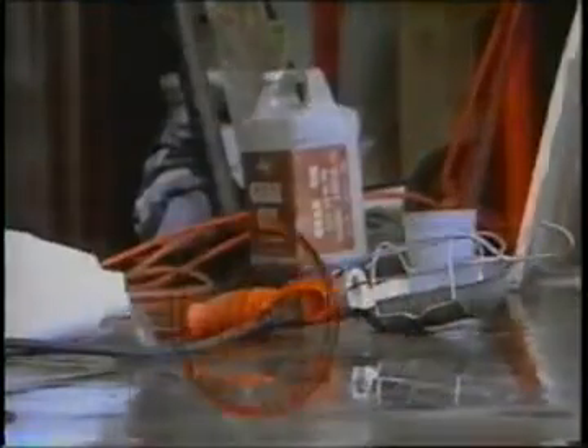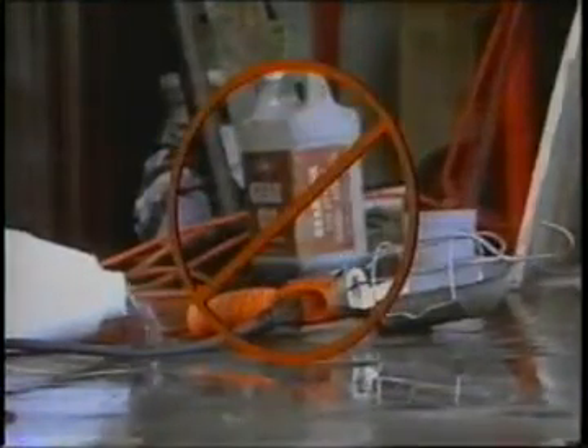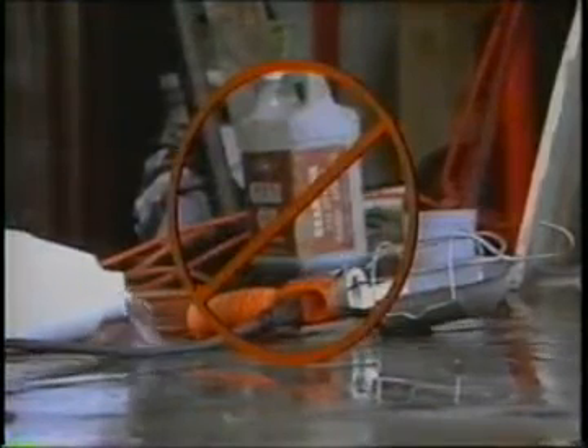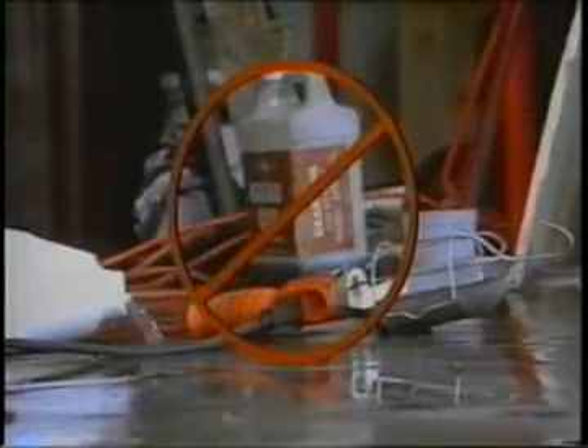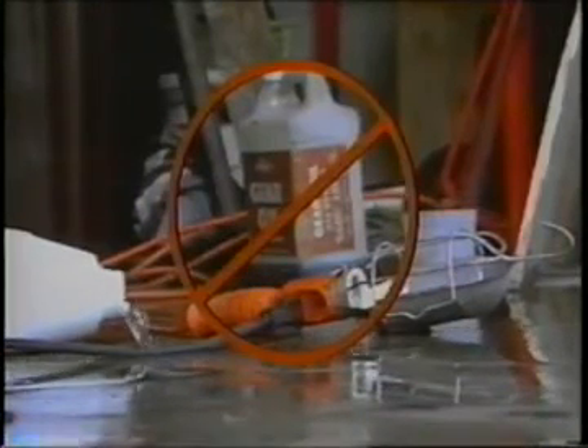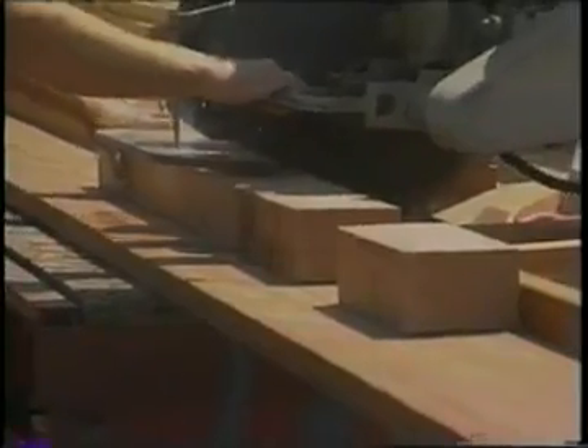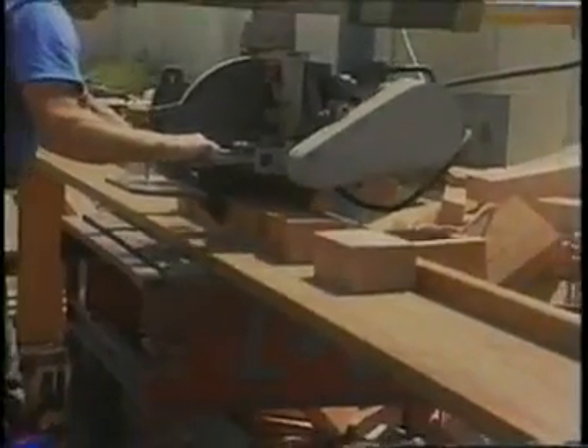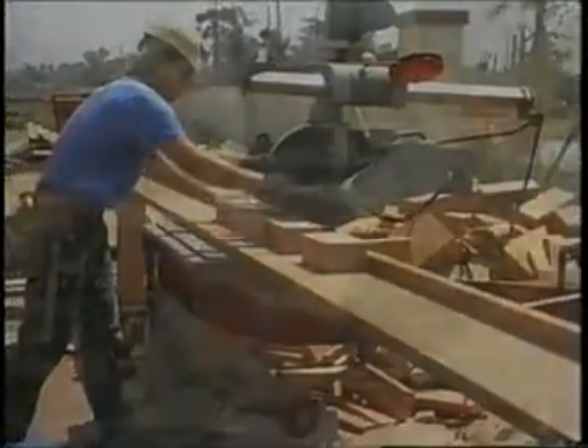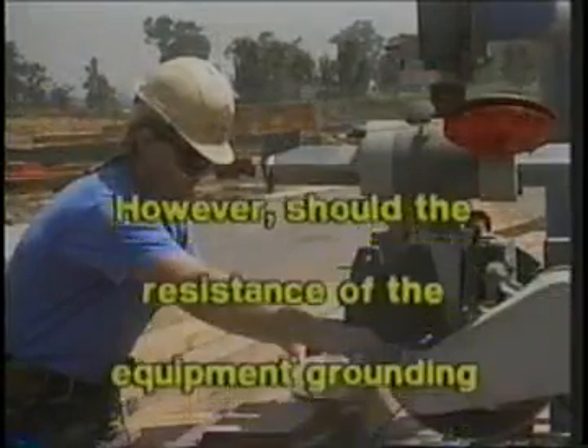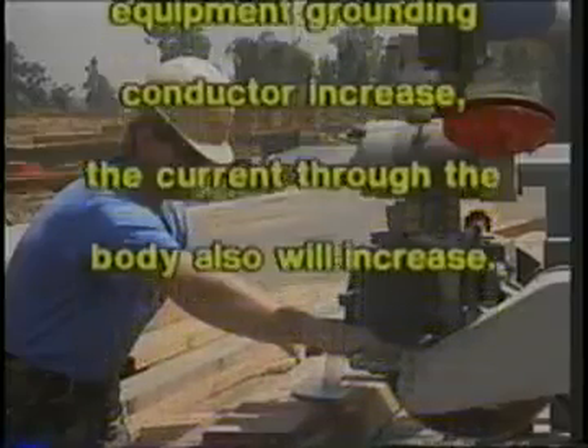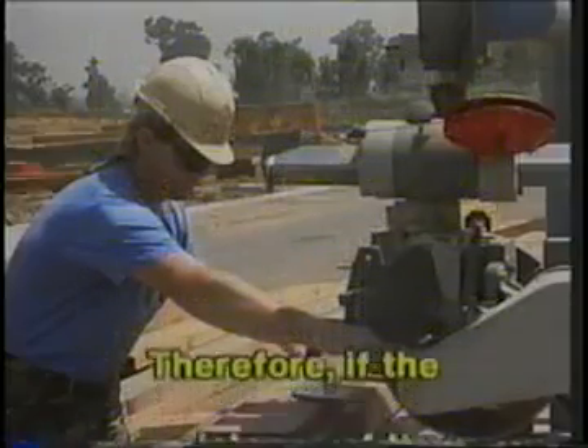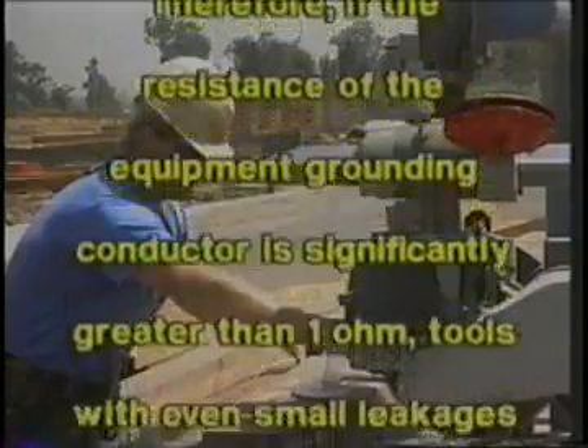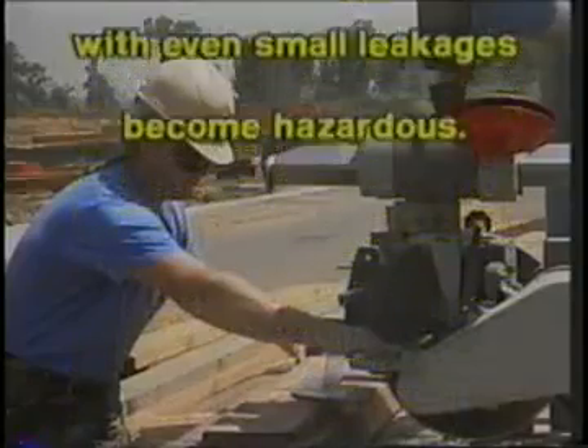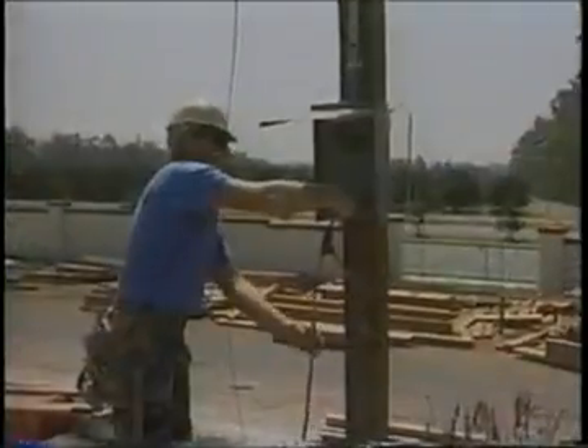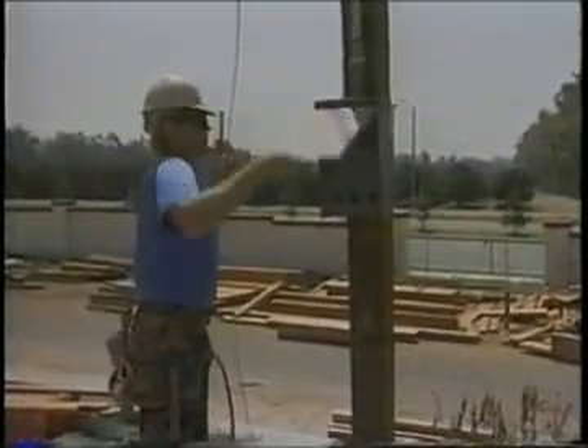When a cord connector is wet, hazardous leakage can occur to the equipment grounding conductor and to humans who pick up that connector if they also provide a path to ground. Such leakage is not limited to the face of the connector, but also develops at any wet portion of it. When the leakage current of tools is below 1 milliampere and the grounding conductor has a low resistance, no shock should be perceived. However, should the resistance of the equipment grounding conductor increase, the current through the body also will increase. Therefore, if the resistance of the equipment grounding conductor is significantly greater than 1 ohm, tools with even small leakages become hazardous. GFCIs can be used successfully to reduce electrical hazards on construction sites.